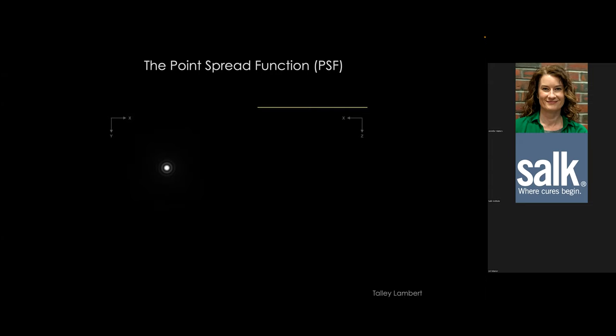The image is three-dimensional, so we also need to think about what the PSF looks like in the axial direction. To visualize this, we demagnify our point and perform optical sectioning — similar to what a confocal does — collecting images as we move through focus and reconstructing the axial PSF on the right-hand side of the display.